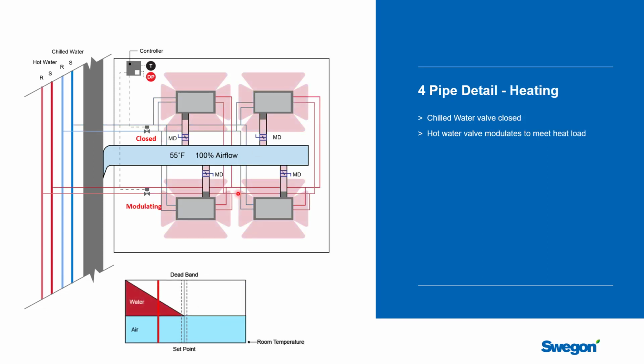The reverse will be true if the beam goes the other way and the zone temperature drops and we need to add heat. What would happen here is that the chilled water valve first would be closed, and if the temperature continued to drop, then we would start to modulate the hot water valve. And the first thing the heat that's going in these coils is going to do is to warm this 55-degree air up to 75 degrees. It's actually providing a cooling effect all the time. We have to negate that first.